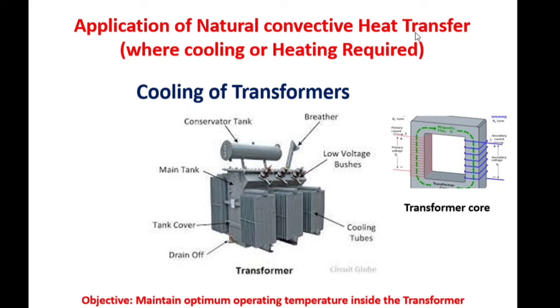Applications of natural convective heat transfer are generally where cooling or heating is required. One example is the cooling of a transformer. Observe the three-dimensional view of an electrical transformer. An electrical transformer consists of a transformer tank and transformer radiator, including cooling tubes. The transformer tank consists of electrical windings and transformer core. The objective of transformer cooling is to maintain an optimum operating temperature inside the transformer — generally 50 to 60 degrees Celsius under normal load conditions.